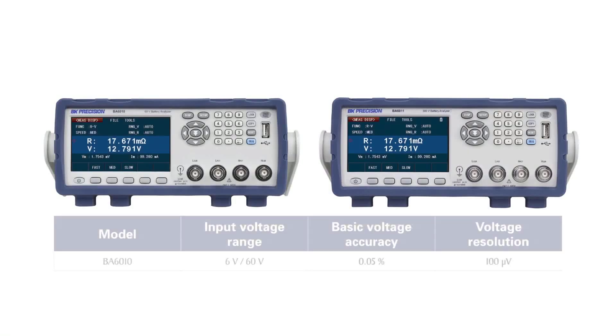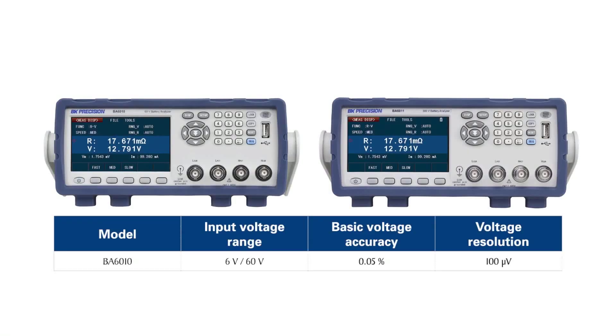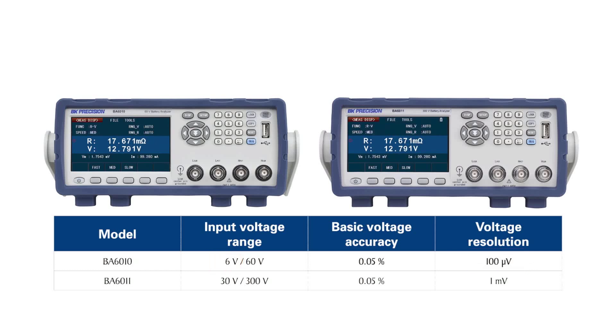The series includes two models: the BA6010 and the BA6011. Both models have two voltage ranges that allow the user to take advantage of higher resolution in the lower ranges. The BA6010 has its best resolution of 100 microvolts in the 6-volt range, while the BA6011 has its best resolution of 1 millivolt in the 30-volt range.